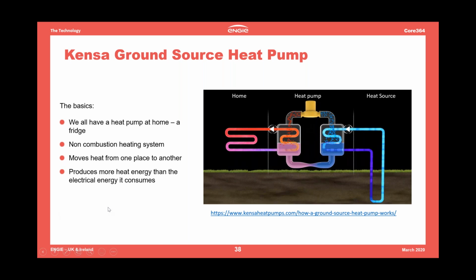In our solution, you have one large array connected to multiple heat pumps in multiple properties. The heat source, typically boreholes when doing large-scale deployment, has fluid circulating around them picking up latent heat from the ground - typically gaining about 5 degrees of heat. All these boreholes combine together leaving us with riser pipework, which is then able to flow up and down the tower blocks, going to each individual heat pump.